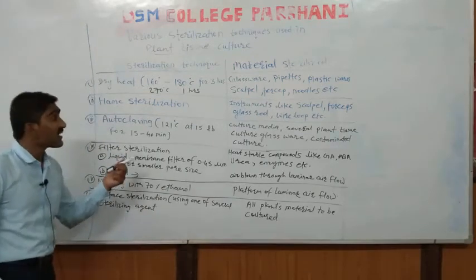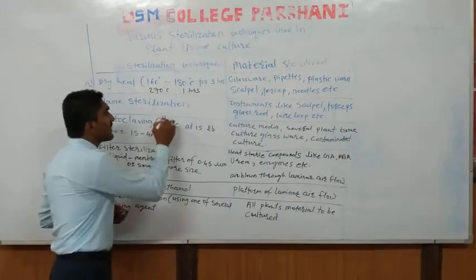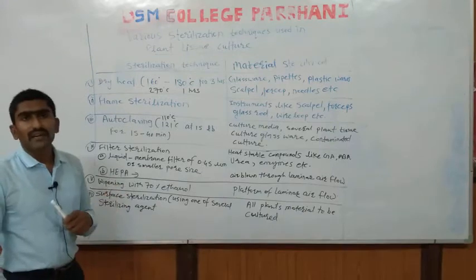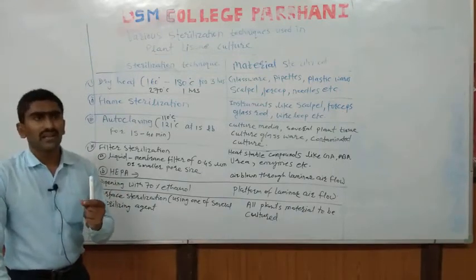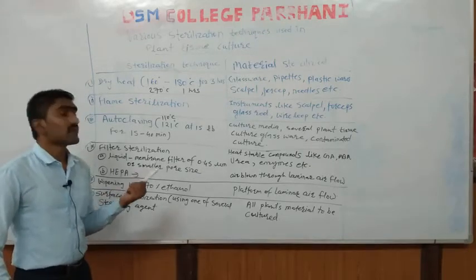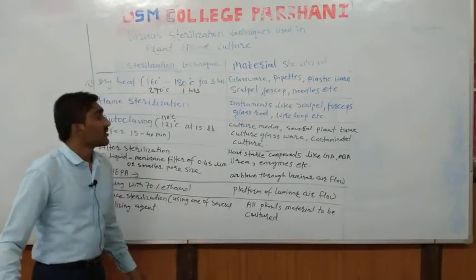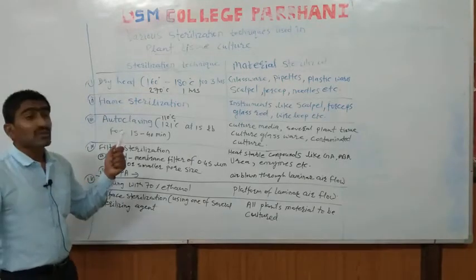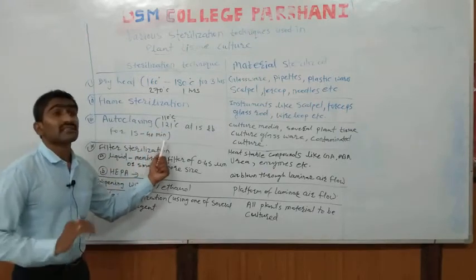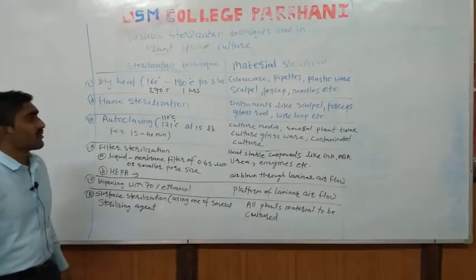Sometimes we keep media for up to 40 minutes and reduce the temperature to 110°C. This condition is applied when the media contains heat-sensitive elements — if we raise the temperature, those elements may be lost. So for such media, we keep it at 110°C for a longer time of 40 minutes. This is the general principle of autoclaving.